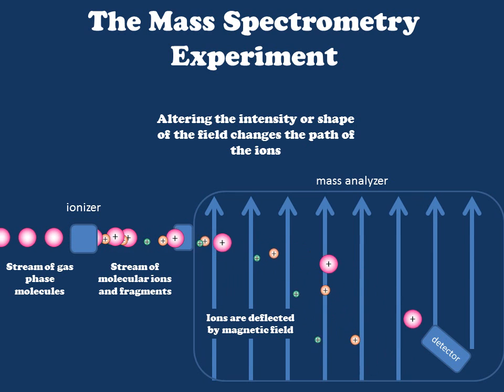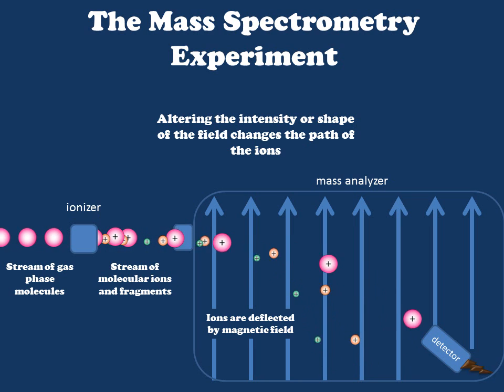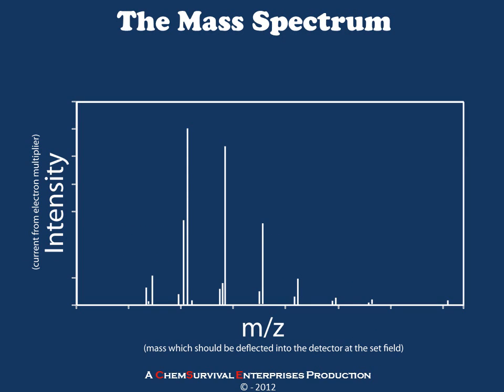If we increase the field strength one more time, the molecular ions are now striking the detector, which generates a new current. So at this particular field strength, the computer workstation will know that there is some type of ion reaching the detector. Creating a plot of intensity versus m/z gives us our mass spectrum. What you're really looking at is a plot of the amount of current exiting the electron multiplier as a function of the field setting — the field setting tells us what mass should be exiting at that time, and the electrical current tells us whether any ions of that particular mass are present in the sample.